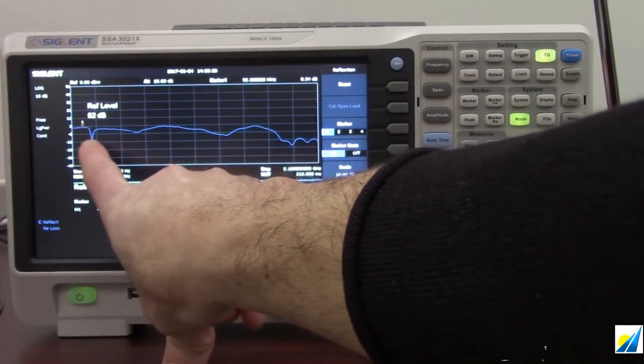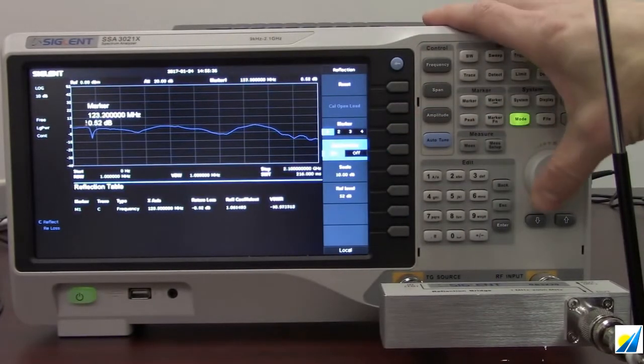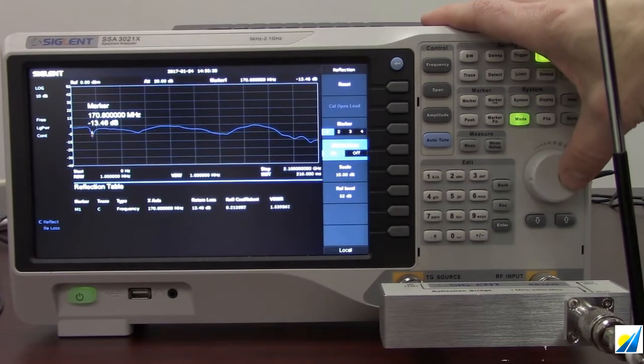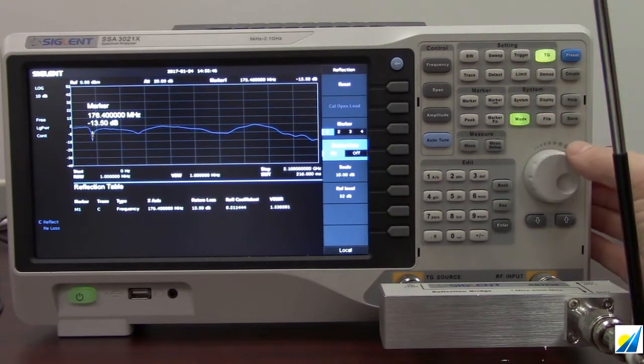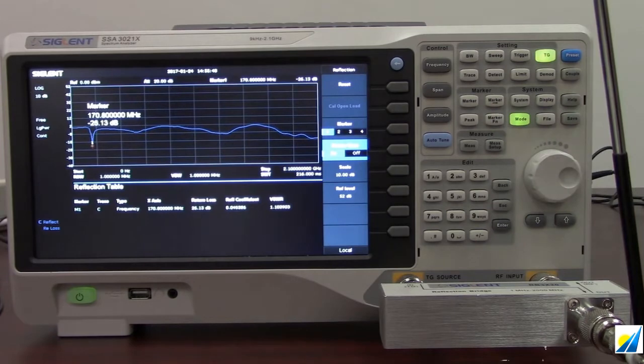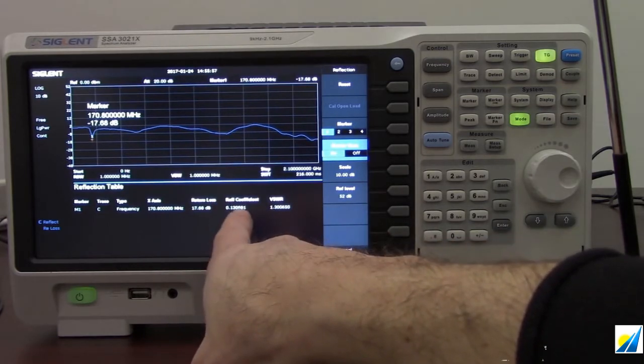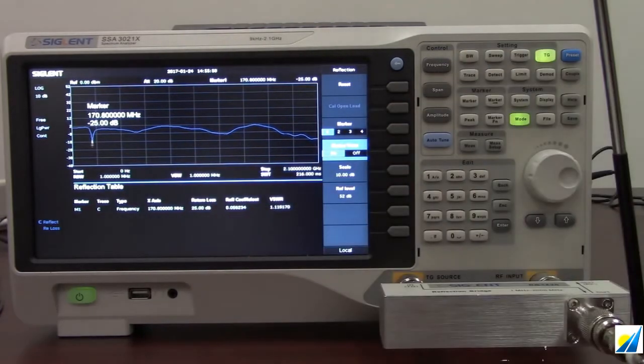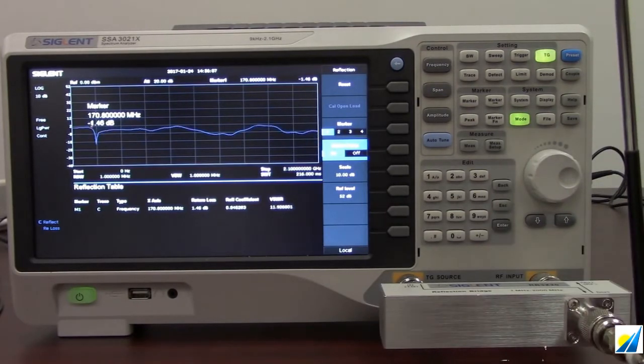Frequencies where we're getting direct reflection are going to be shown as dips, and you can see there's a very nice dip here. I'm going to turn the marker on and rotate it to that lowest point, which will measure the VSWR at that particular point. That's a pretty good reading — we've got a VSWR of around 1.1. This gives our return loss value and our reflection coefficient. This particular antenna in this configuration resonates most effectively at 170.8 MHz.